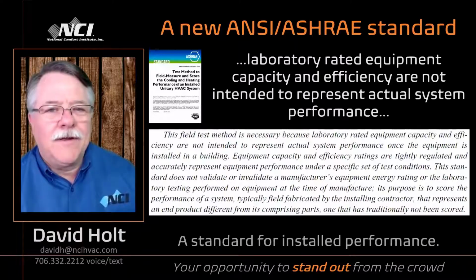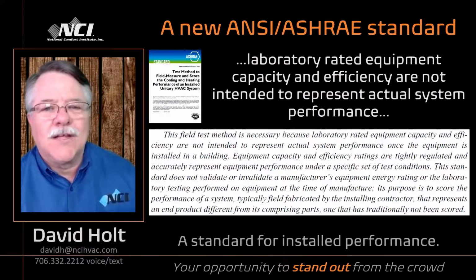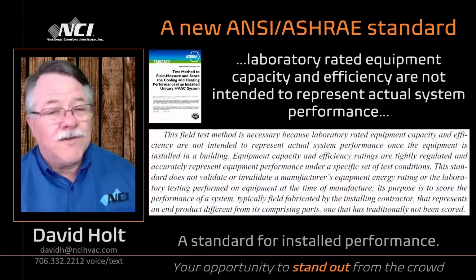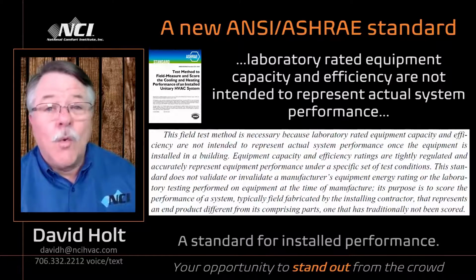But I promise you one thing that's for sure. The manufacturer does not endorse some of our installation methods either. Because if you read the installation manuals, if you read what it says about setting the fan speed, if you read what it says about what airflow is produced at certain static pressures, you would find that they are telling you the right stuff in their manual. We're just not paying attention to it. As contractors, we got to fix that. We can do better. We need to stand out from the crowd and not deliver these 57%ers.